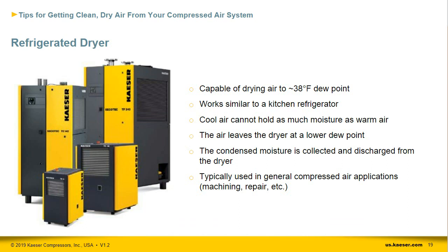Refrigerated dryers are a basic part of many compressed air treatment plans. The majority of condensate held in the compressed air is removed at the compressor aftercooler or after the refrigerated dryer, meaning that these dryers are capable of providing a workable dew point for most compressed air applications.